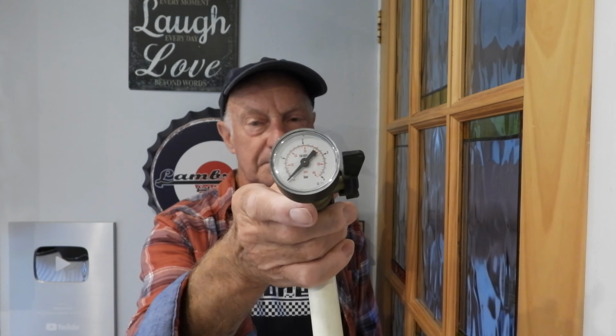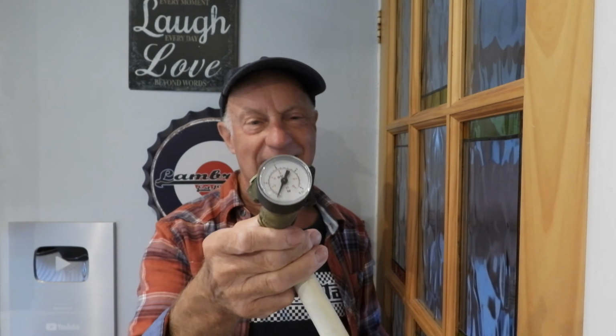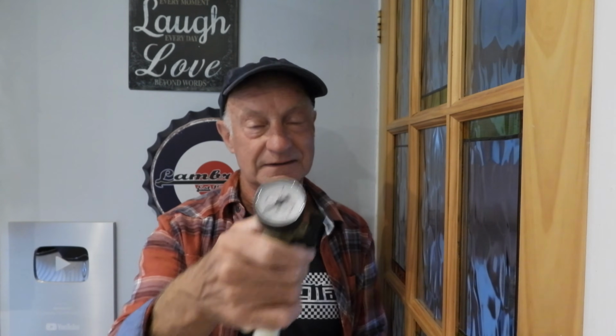The gauge itself. This is the pressure gauge of a combi boiler, and I have known these stick. You think you've got the right pressure and it's not working at all, it's jammed, and you may in actual fact be working on well over pressure because you keep thinking it looks a bit low. I think I'll put a bit more in and a bit more. In actual fact, you're putting more and more in, and this gauge isn't reading properly.